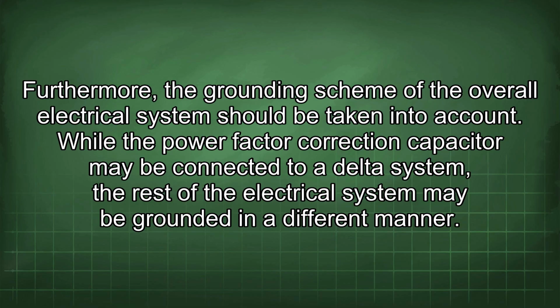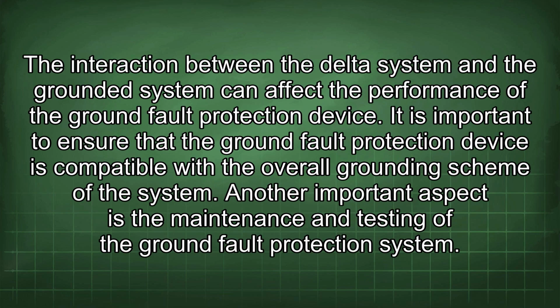Furthermore, the grounding scheme of the overall electrical system should be taken into account. While the power factor correction capacitor may be connected to a delta system, the rest of the electrical system may be grounded in a different manner. The interaction between the delta system and the grounded system can affect the performance of the ground fault protection device.